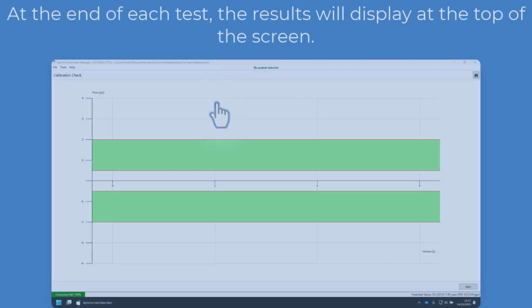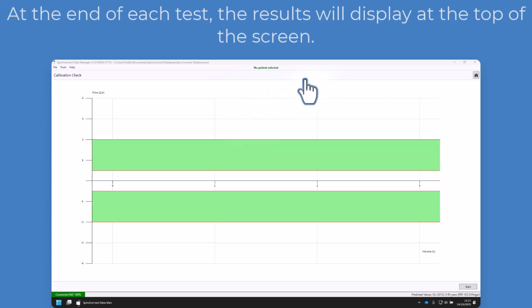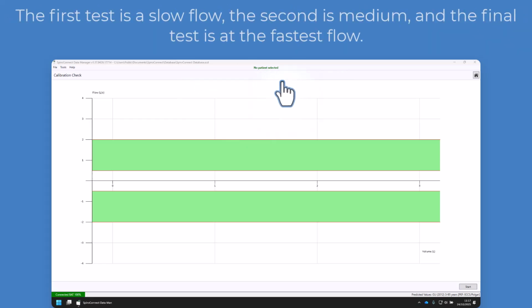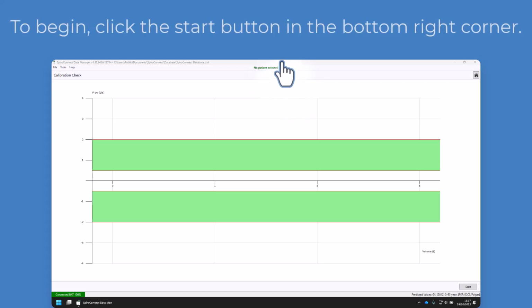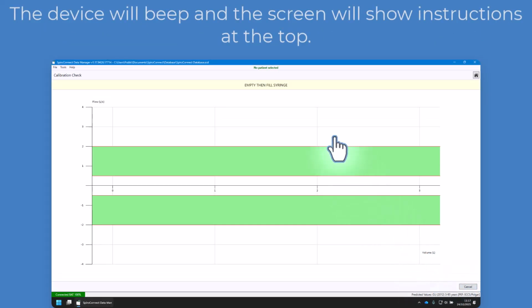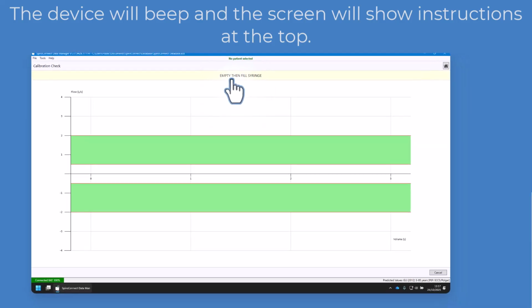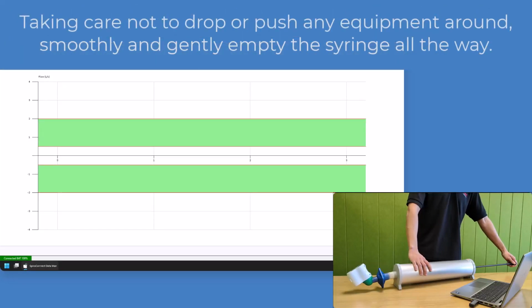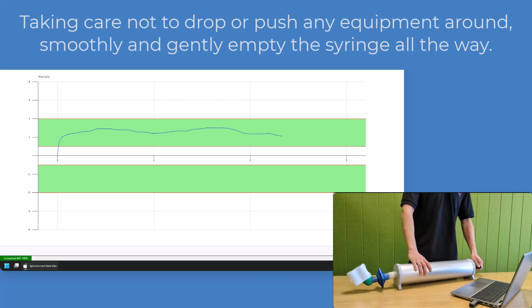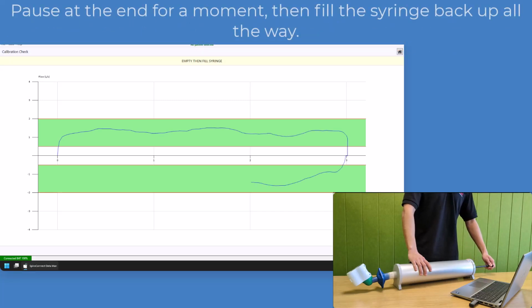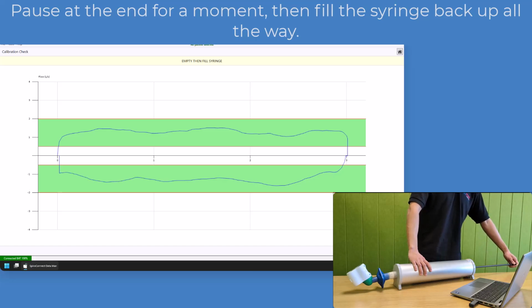At the end of each test, the results will display at the top of the screen. The first test is a slow flow, the second is medium, and the final test is at the fastest flow. To begin, click the Start button in the bottom right corner. The device will beep and the screen will show instructions at the top. Taking care not to drop or push any equipment around, smoothly and gently empty the syringe all the way. Pause at the end for a moment, then fill the syringe back up all the way.